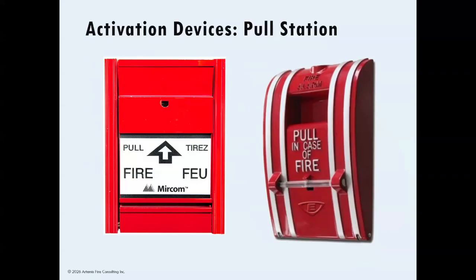And lastly, for activation devices, the well-known pull station, which needs to be located at every designated exit from the building. Recent changes in the building code now require these to be located about 1,050 to 1,150 millimeters, or 41 to 45 inches for those of us who still do imperial, from the floor to increase accessibility.